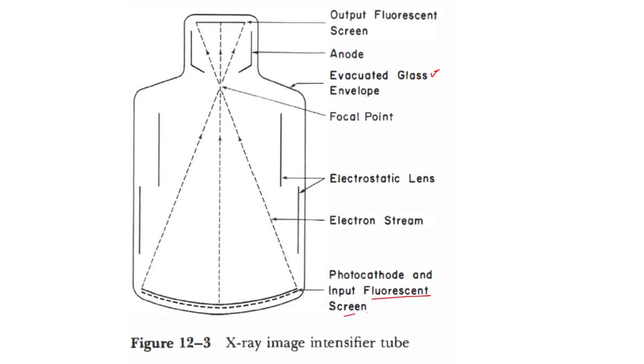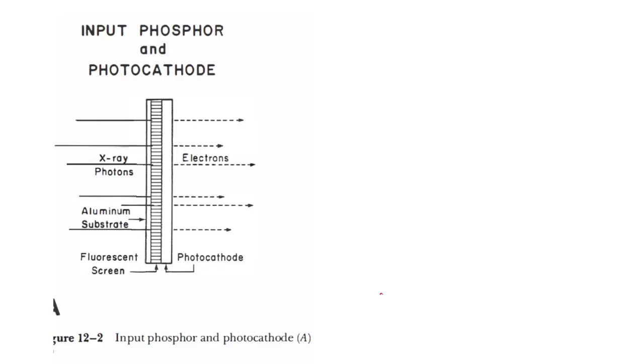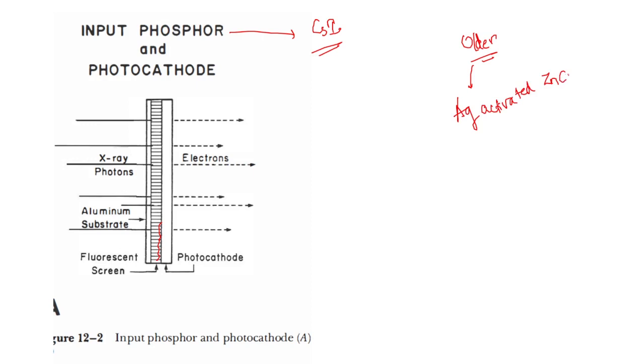Now let us learn about each part in detail. First, the input fluorescent screen or photocathode. This input fluorescent screen is mainly made up of cesium iodide (CsI). Older image intensifiers used silver-activated zinc cadmium sulfide as the input phosphor.